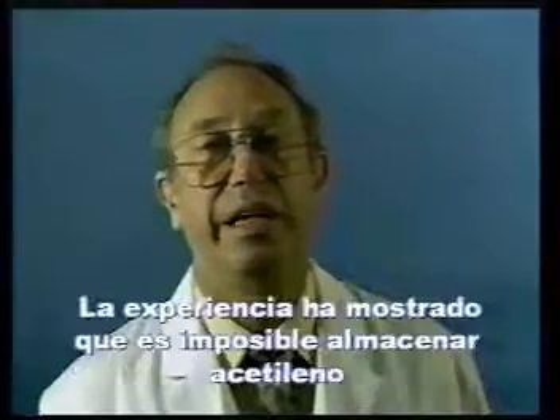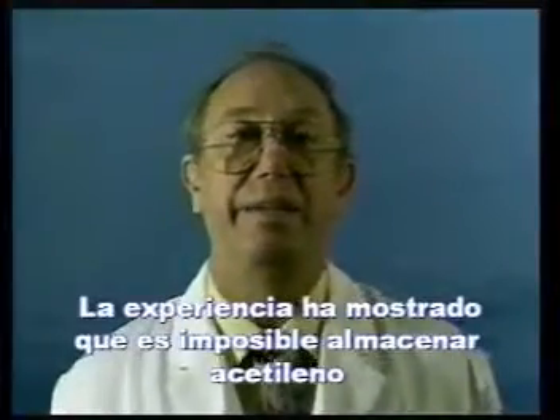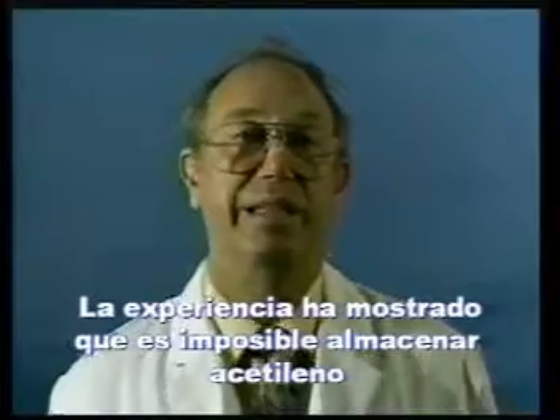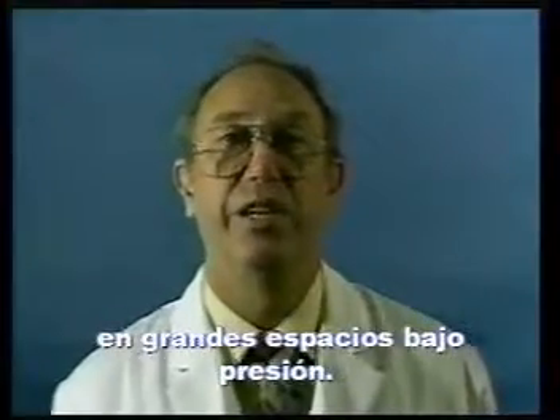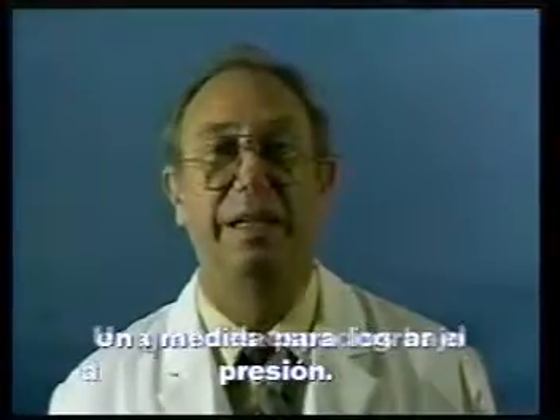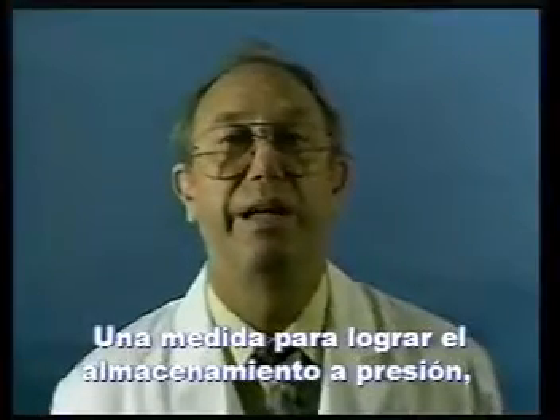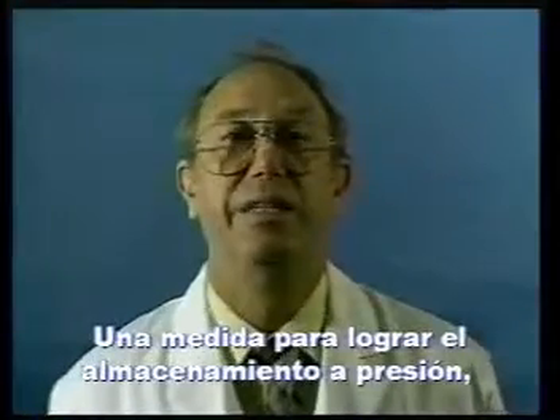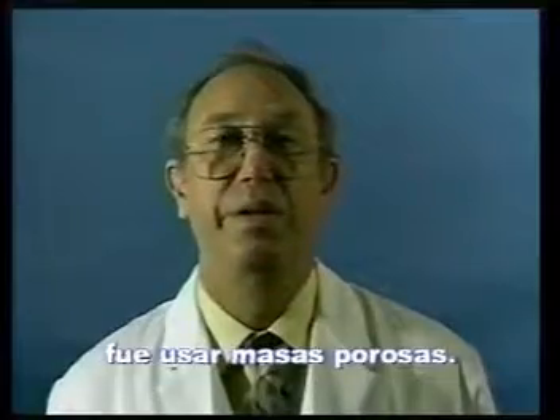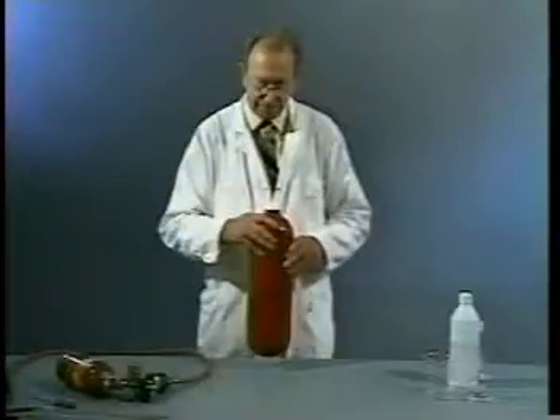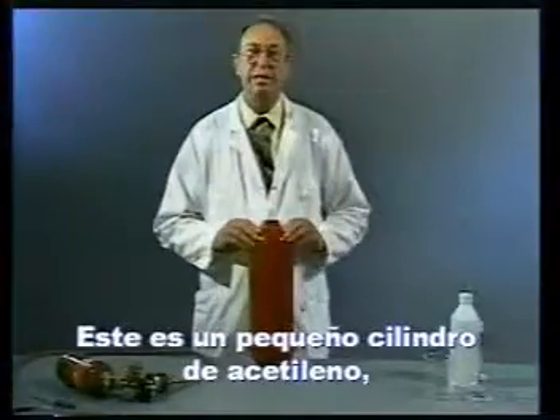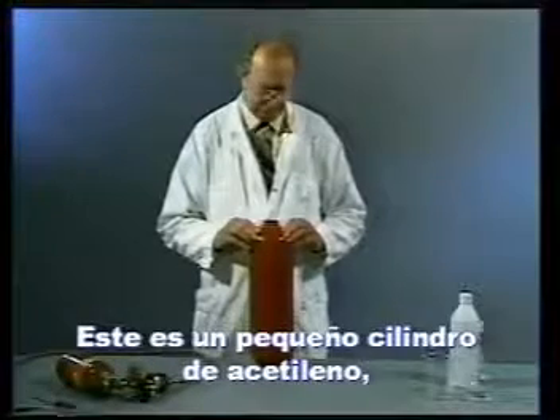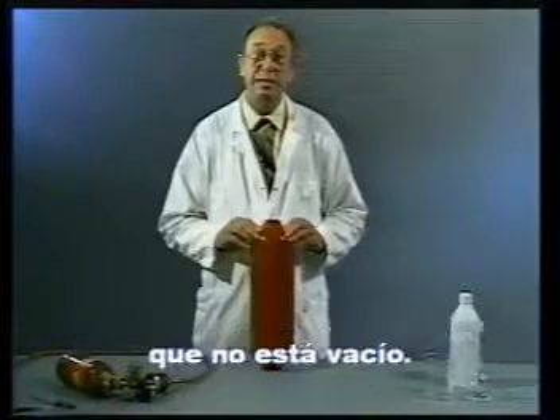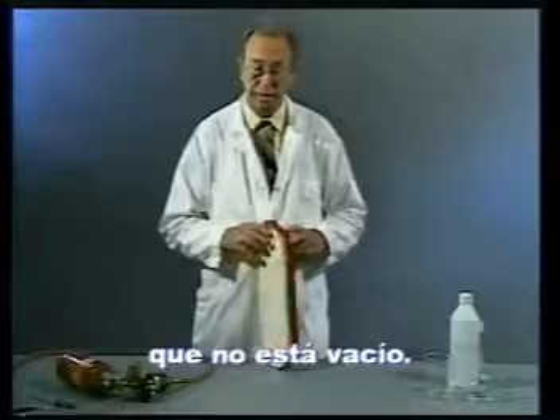Accidents during the years have proven that it is impossible to store acetylene under pressure in larger hollow spaces. One measure to prevent this was to fill the cylinders with a porous mass. Now, here you see is a cylinder, and this acetylene cylinder is not empty.